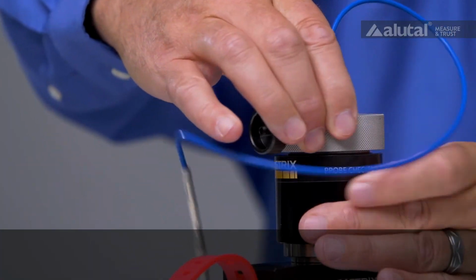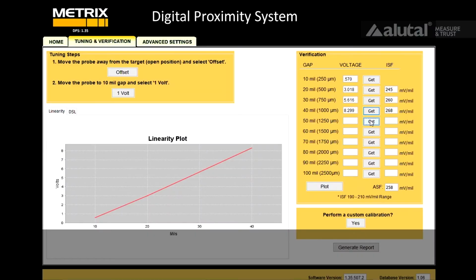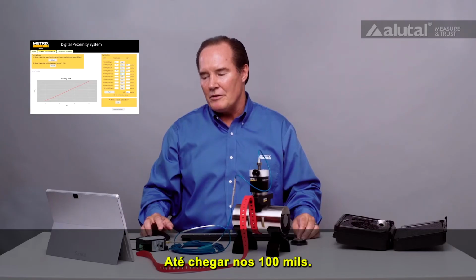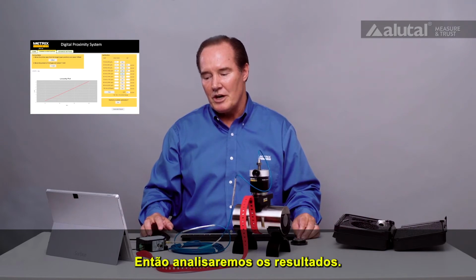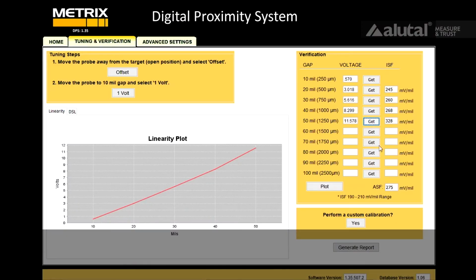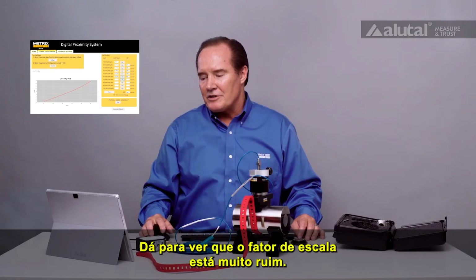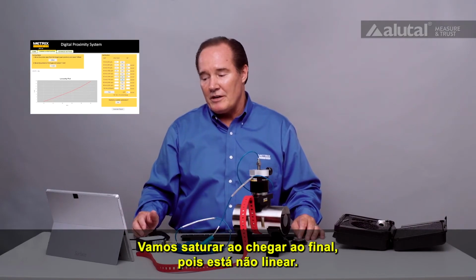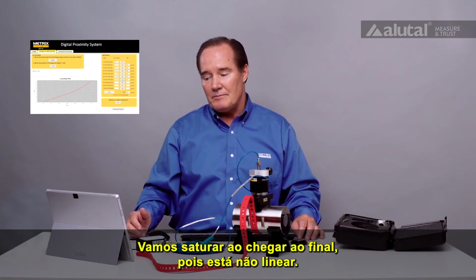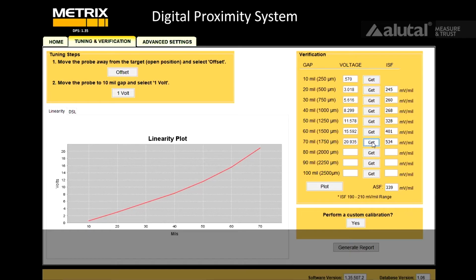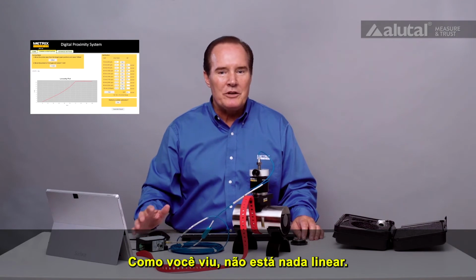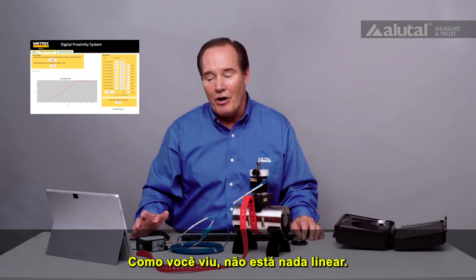And we do this until we get to 100 mils, and then we'll look at our results. You can see the scale factor is way off. We're probably going to saturate by the time we get to the end because it's non-linear. All right, we've taken the data, and what you can see is that it's not linear at all.